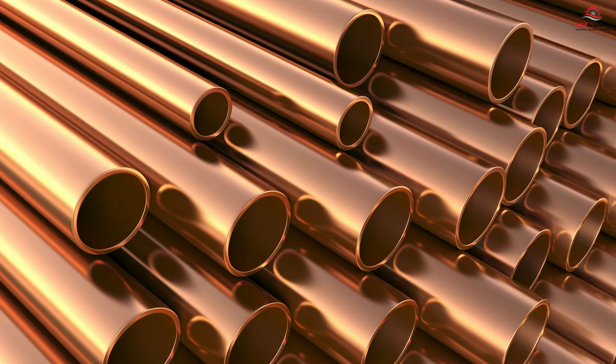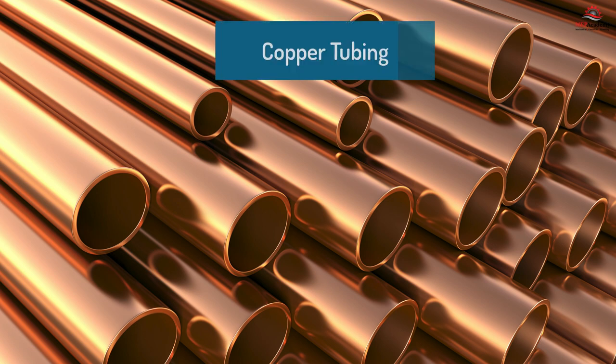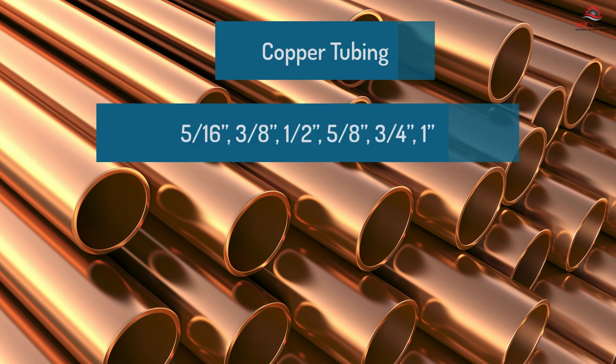We'll cover coil construction. Most coils used in the HVAC industry are constructed using copper tubing, ranging in size from 5/16 inch up to 1 inch OD. You may find 5/8 inch to be the most commonly used size.